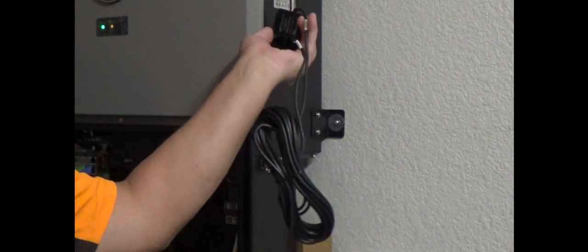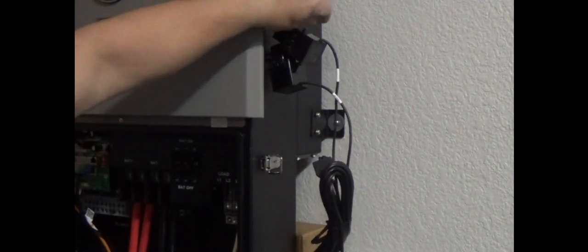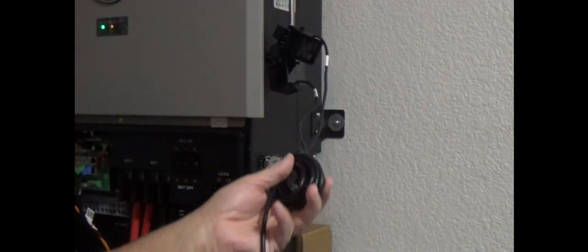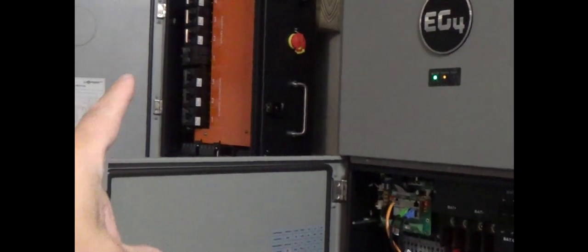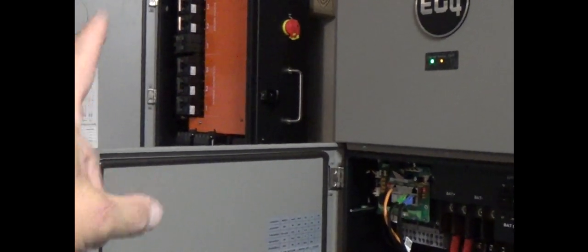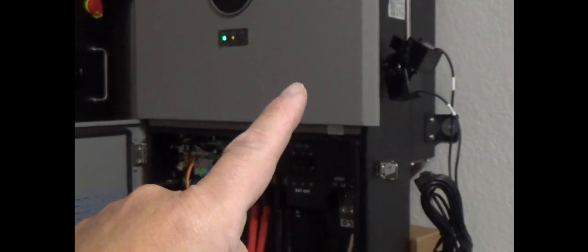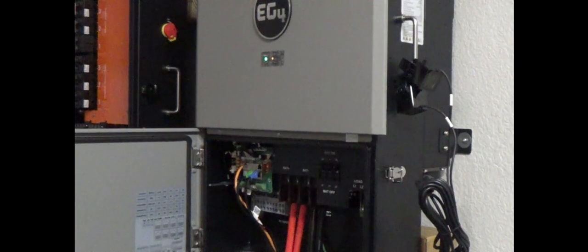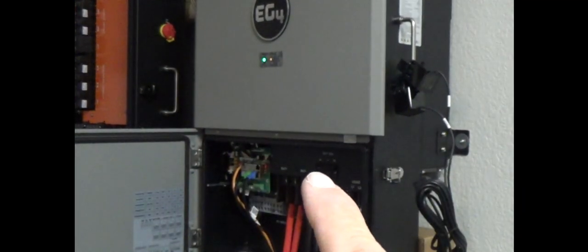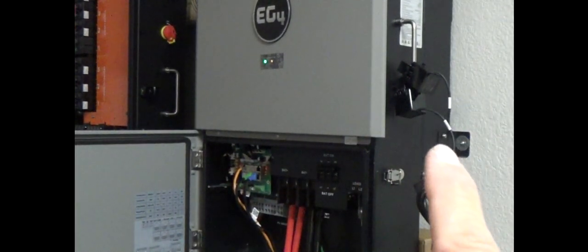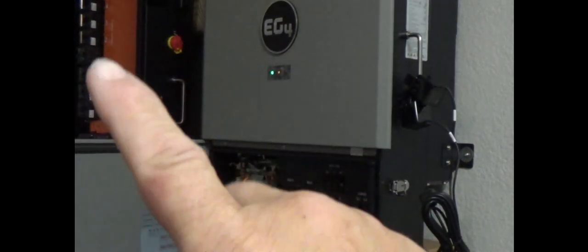I got the CTs sitting out here on the handle grip. If you're using the inverter with the Gridboss, then the Gridboss has built-in CTs, and you don't use these on the inverter. Make sure that everybody knows, if you're using a Gridboss with an inverter, you don't use the CTs on the inverter. The Gridboss has built-in CTs in them.